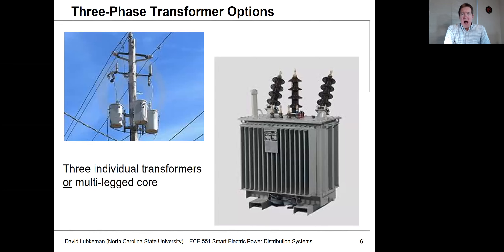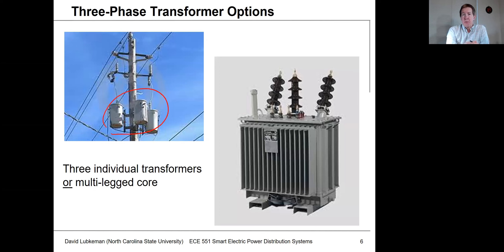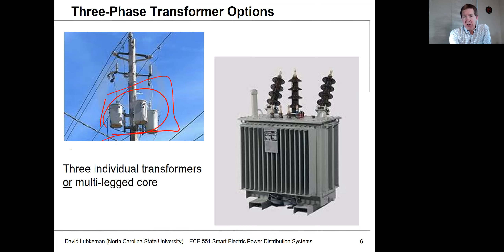As far as how we build a three-phase transformer, there are two different ways. One is to take single-phase transformers and connect them up. Based on how I connect them on the primary and secondary sides, I can get a delta or a Y connection. This approach can take up quite a bit of space, so if space isn't an issue — say mounting on top of a pole — then by all means use three single-phase transformers, which gives the most flexibility.